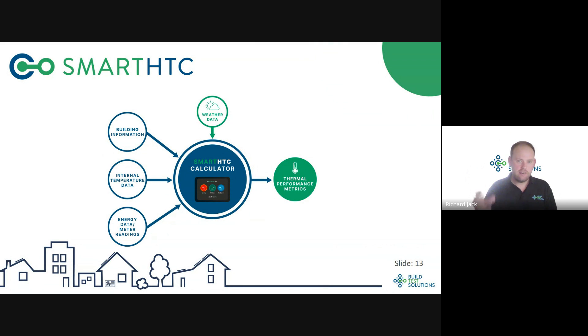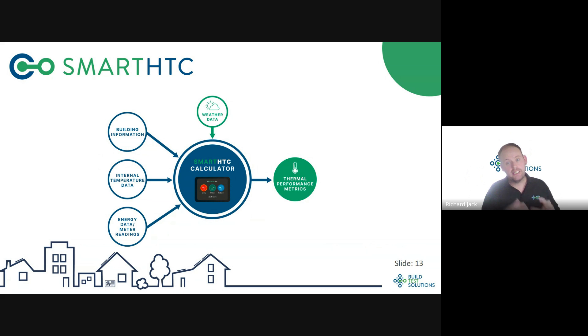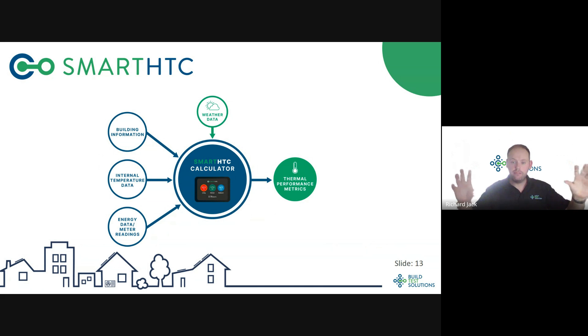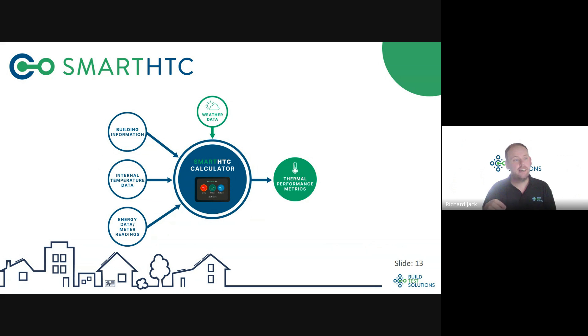Now for the nuts and bolts of using Smart HTC. The concept is: we gather information about the building from a survey, gather internal temperature data and energy consumption data, feed that into the Smart HTC calculator which lives in the cloud, and it fetches local weather data for your site. We process that mountain of data and turn it into thermal performance metrics — particularly measuring the amount of heat lost from the building.